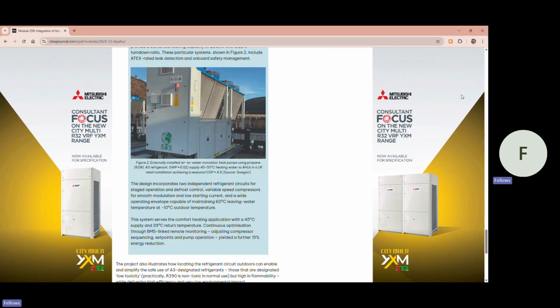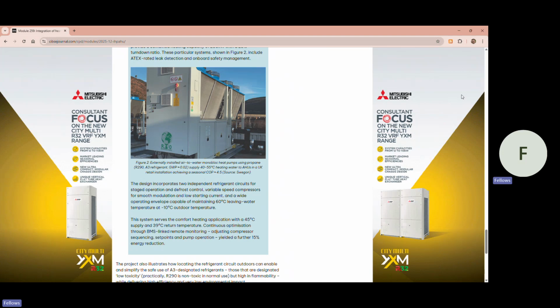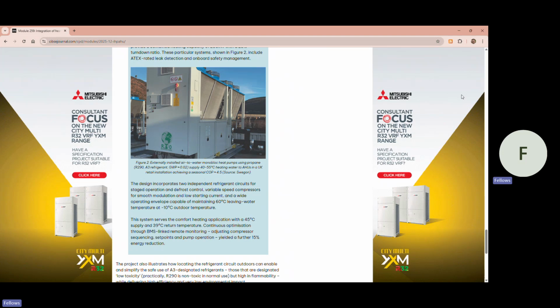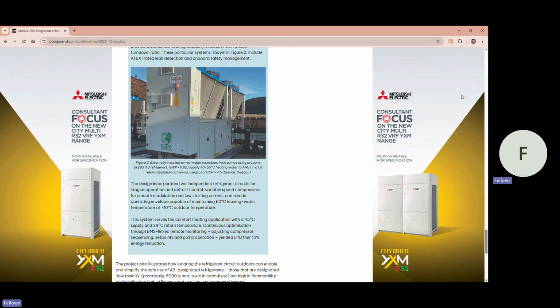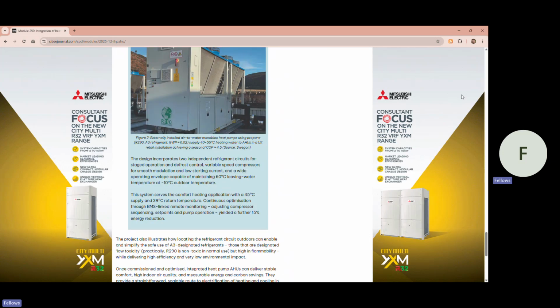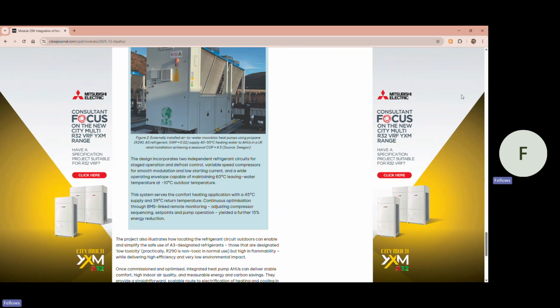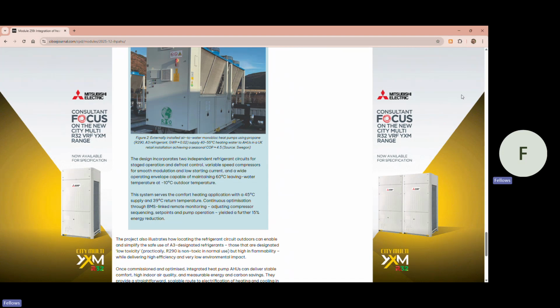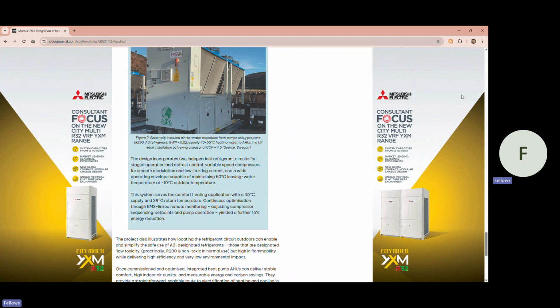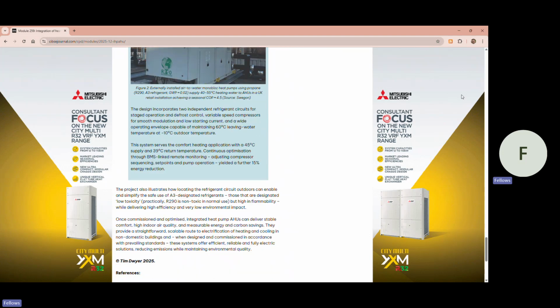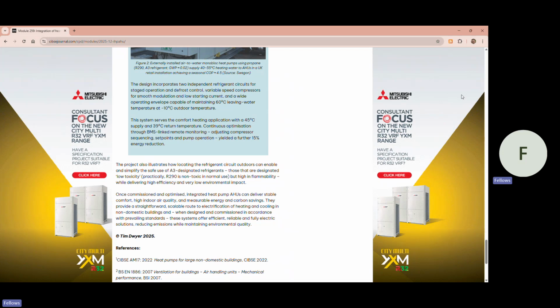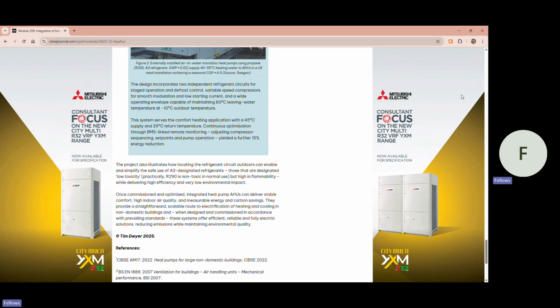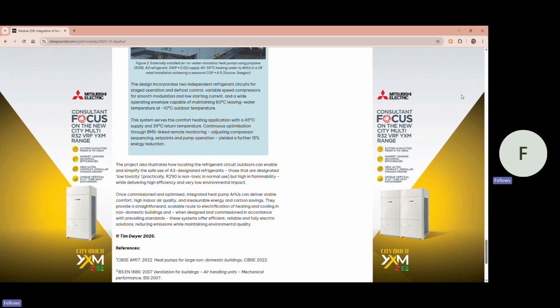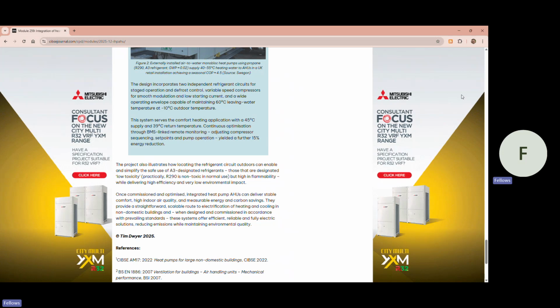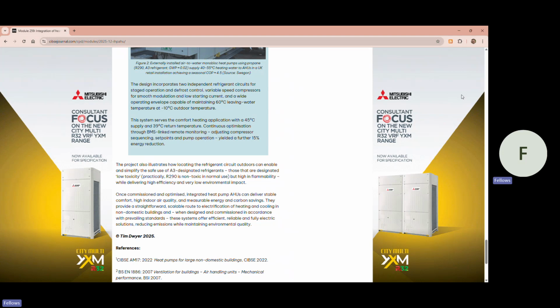The design incorporates two independent refrigerant circuits for staged operation and defrost control, variable speed compressors for smooth modulation and low starting current, and a wide operating envelope capable of maintaining 60 degrees C leaving water temperature at -10 degrees C outside air temperature. This system serves the comfort heating applications with a 45 degrees C supply and a 39 degrees C return temperature. Continuous optimization through BMS-linked remote monitoring, adjusting compressor sequencing, set points and pump operation, yielded a further 15% energy reduction. The project also illustrates how locating the refrigerant circuit outdoors can enable and simplify the safe use of A3 designated refrigerants, those that are designated low toxicity. Practically, R290 is non-toxic in normal use, but high in flammability, while delivering high efficiency and very low environmental impact.